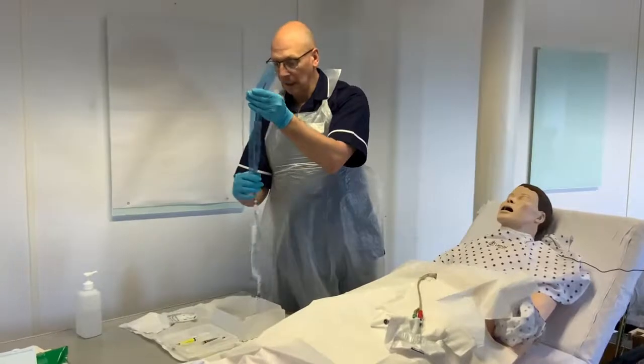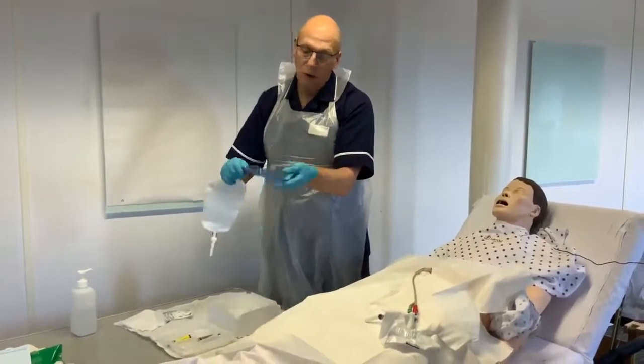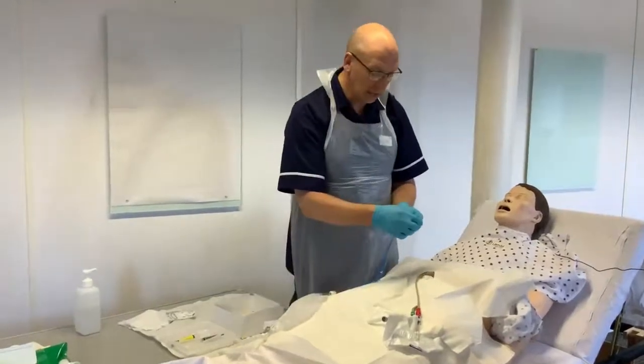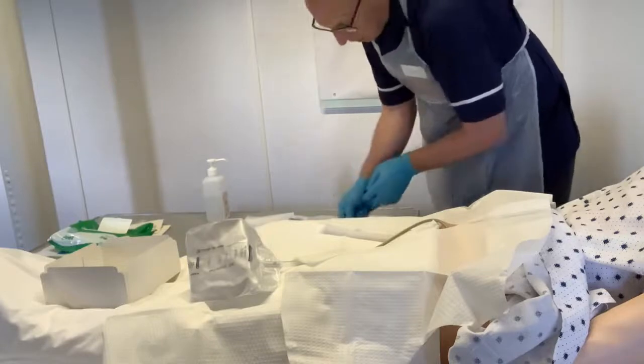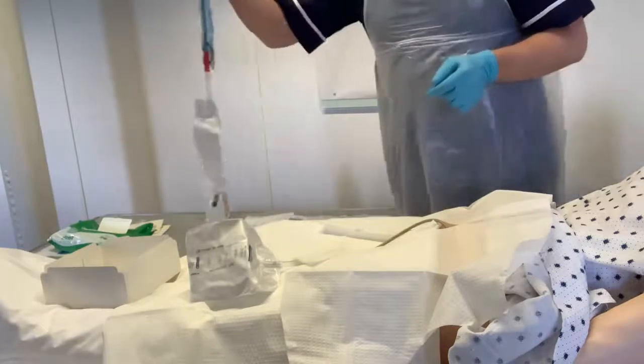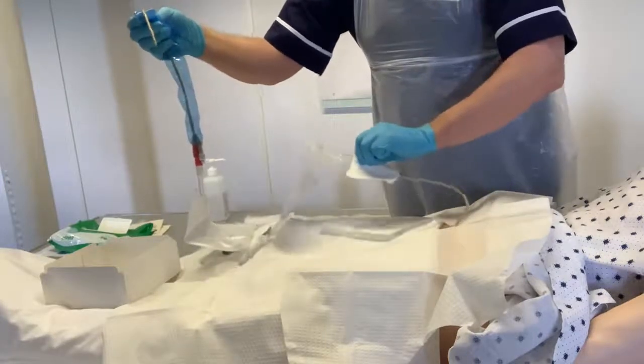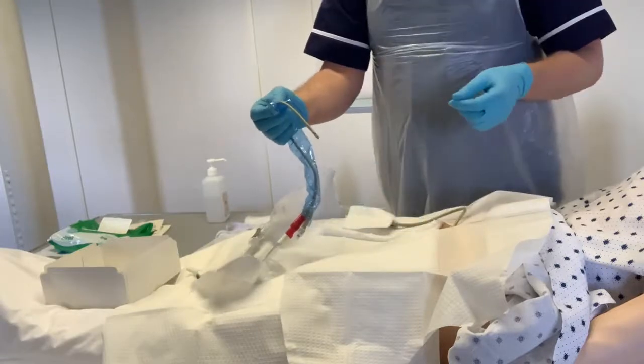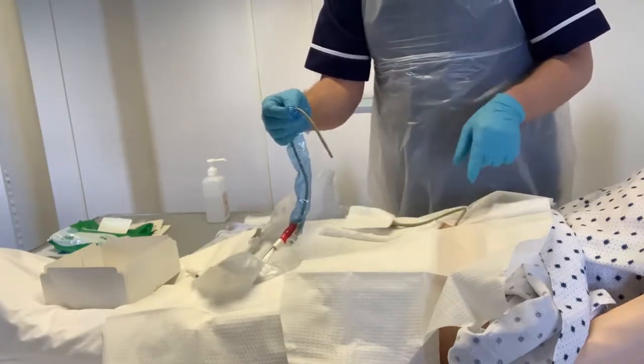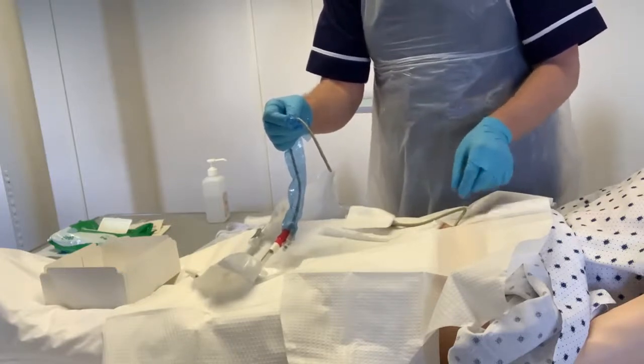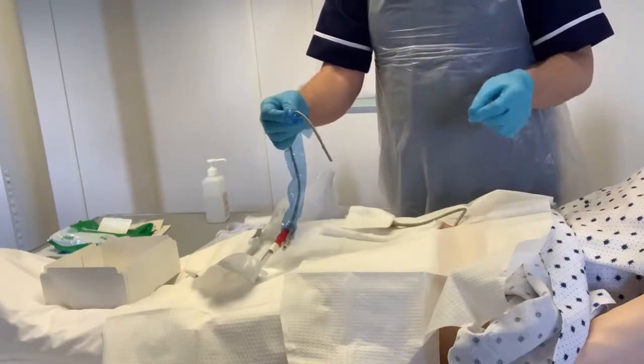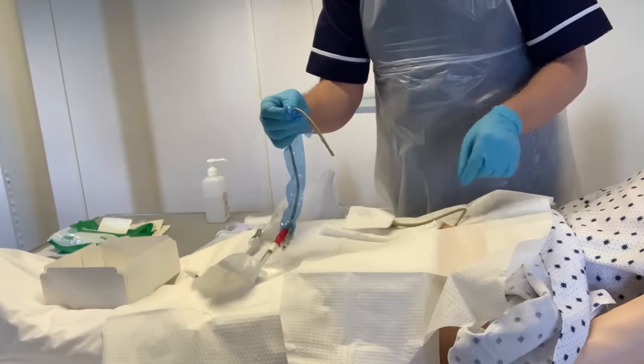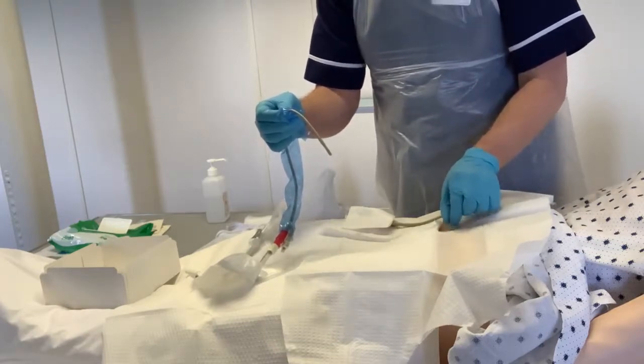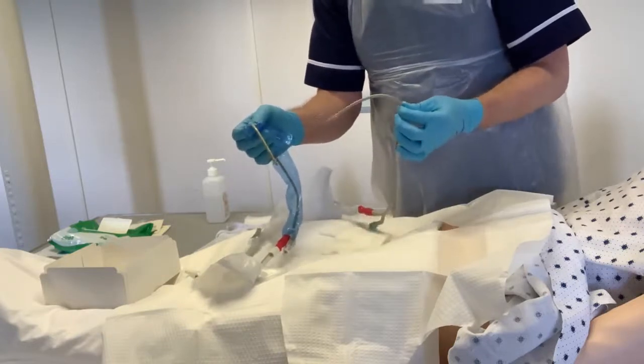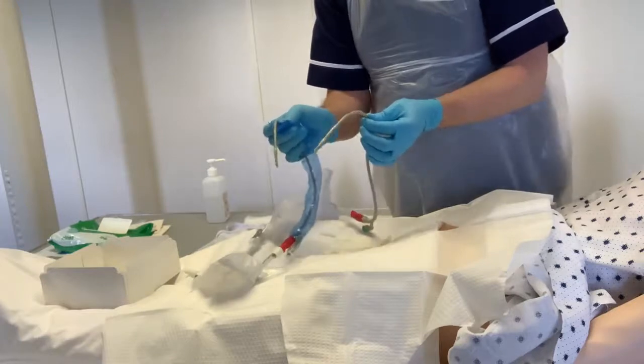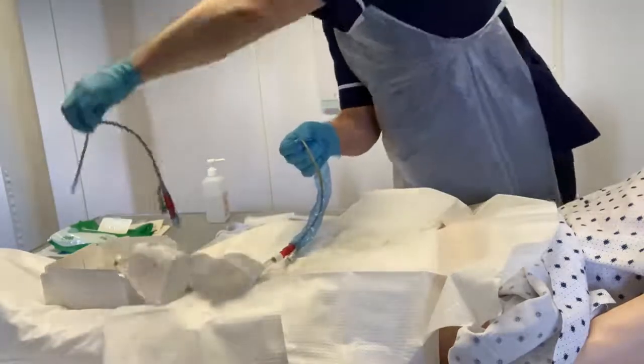So the next thing you're going to do, you've got to be prepared that once you remove your one catheter, you're ready to insert the second. Put some lubricant on the end of your catheter and bring it up. The idea is that you need to remove the old catheter and insert the new catheter within a very small period of time. Observe the track that the old catheter is going on, and gauge the length of the catheter that's actually in the skin. So hold it close to the skin and remove it, and look for signs of incrustation on there, but also gauge the length that's in there.